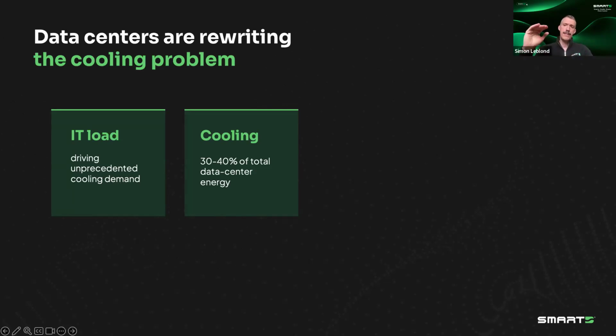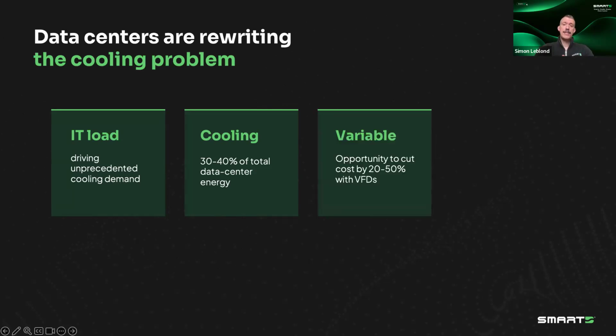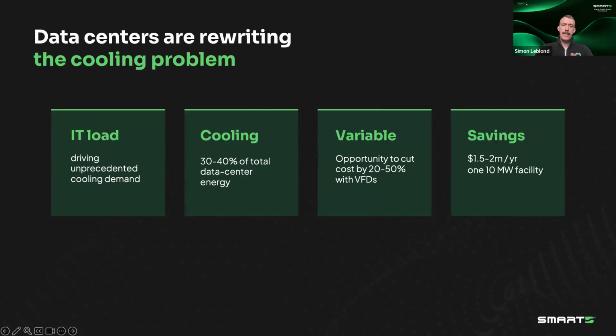So, to give you an idea, best-in-class hyperscalers run at about 1.2 PUE, industry average around 1.5. And what that implies in terms of money, if you have a 10 megawatt IT facility at a PUE of 1.5, you're drawing roughly 5 megawatt just for cooling. So $4.4 million a year at 10 cents a kilowatt. So definitely makes it quite interesting to address variable loads with VFDs and the opportunity to save money, 20 to 50% less energy using those VFDs. That's roughly one and a half, $2 million a year for that 10 megawatt facility.